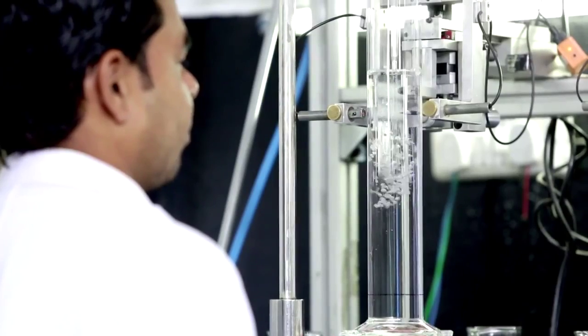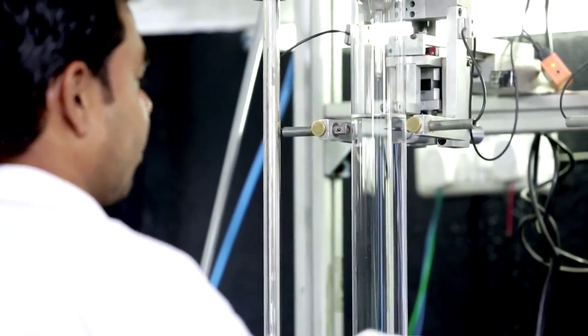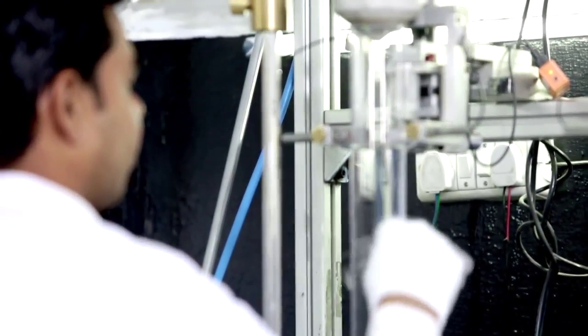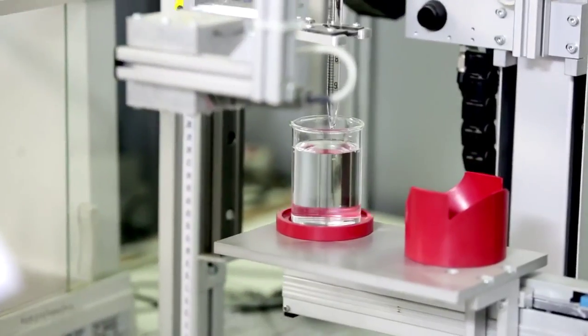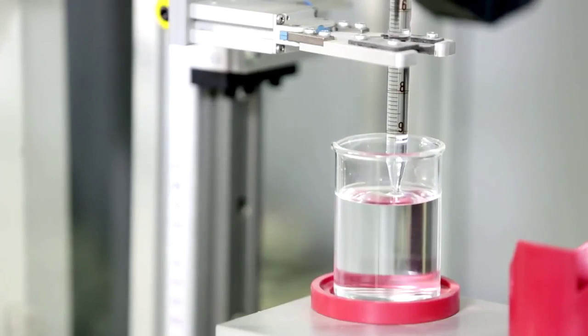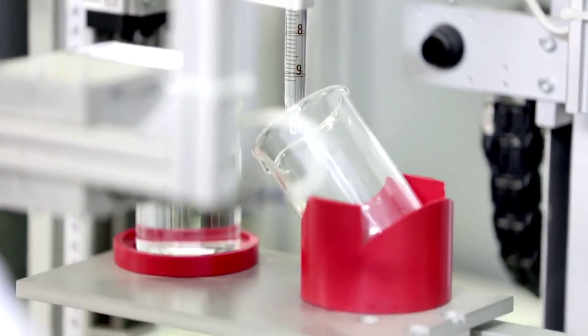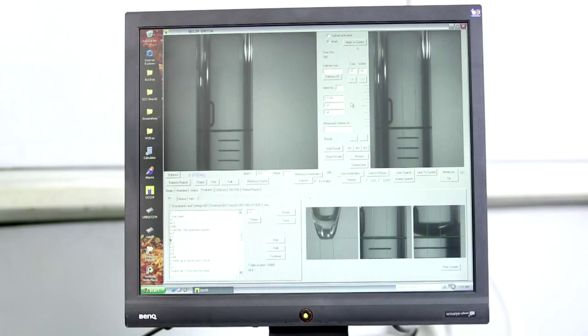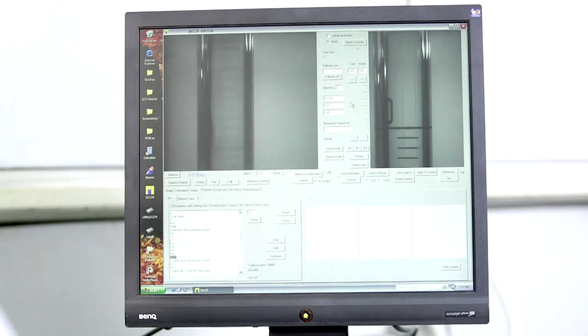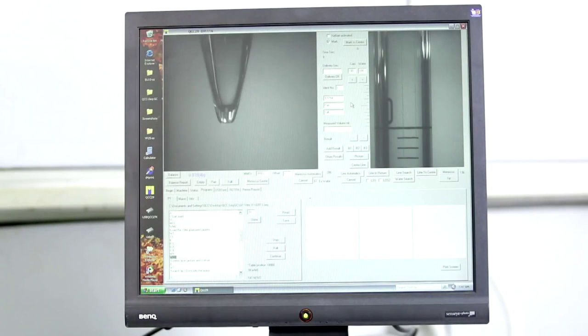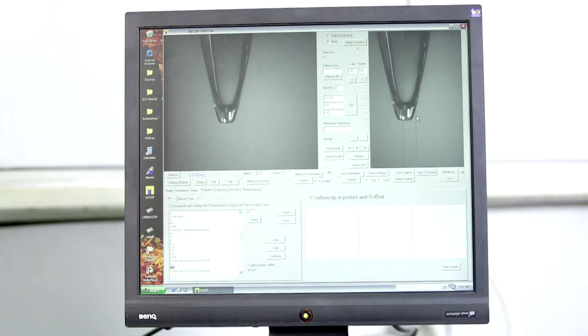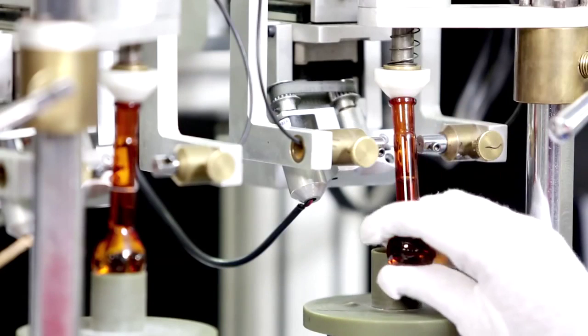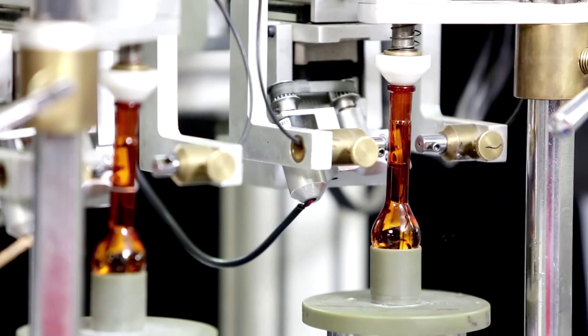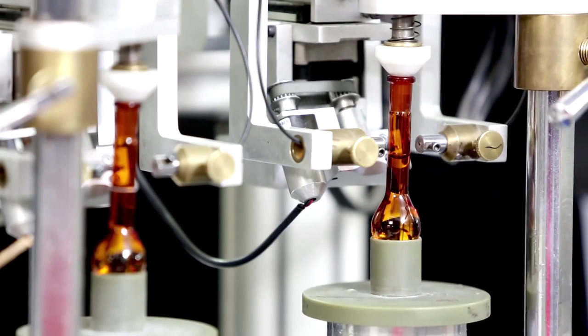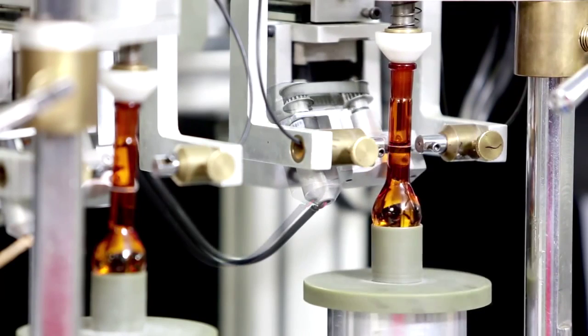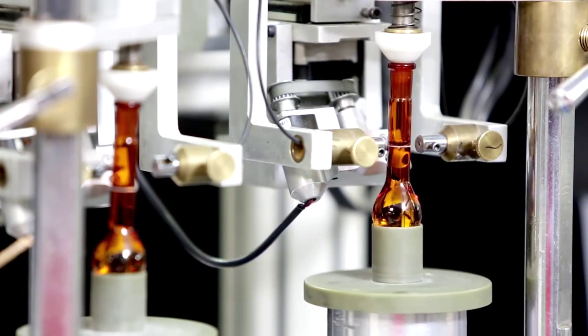All the calibration in the laboratory is done by deionized water. The highly sophisticated machines fill up and drain glassware with deionized water to the capacity up to 0.001 milliliters. Not to forget, with absolute accuracy, each and every flask, burette, and pipette is marked at the precise position, taking into consideration the amount and temperature of air and water.